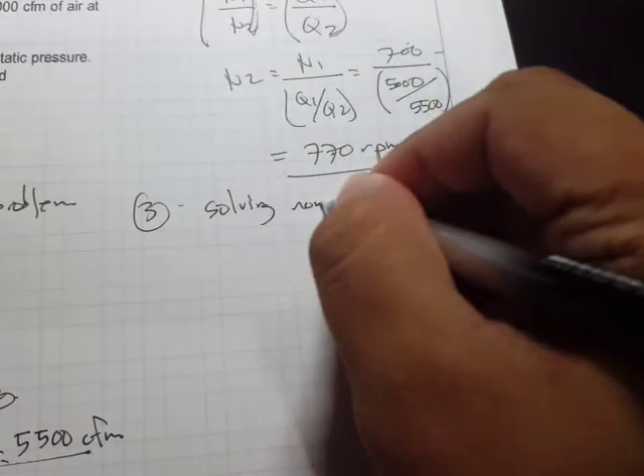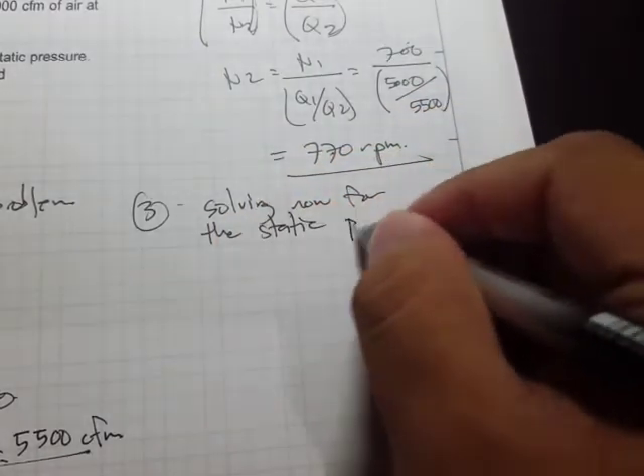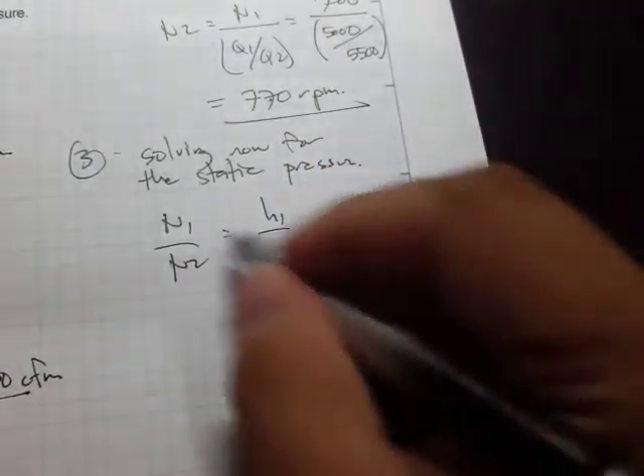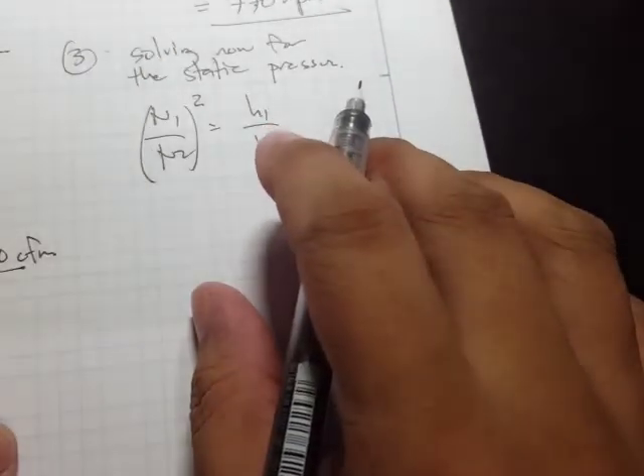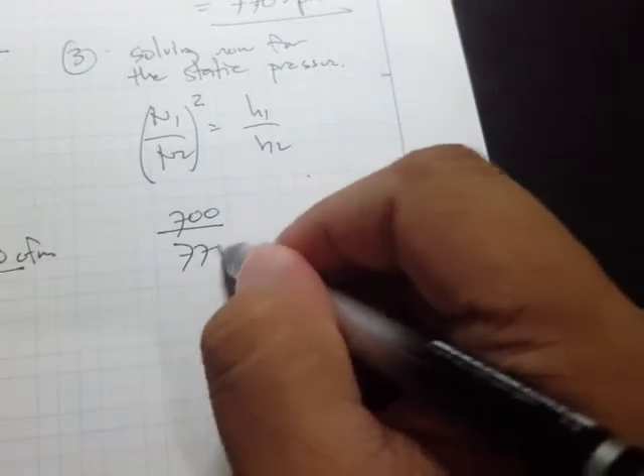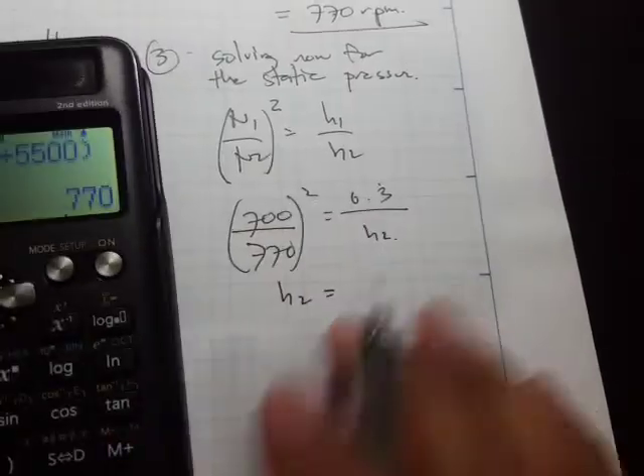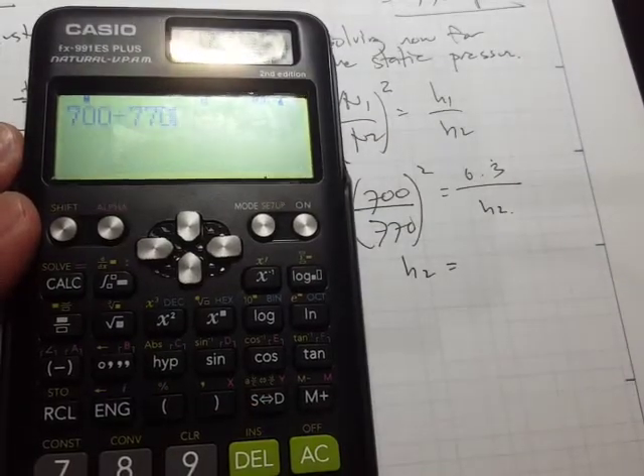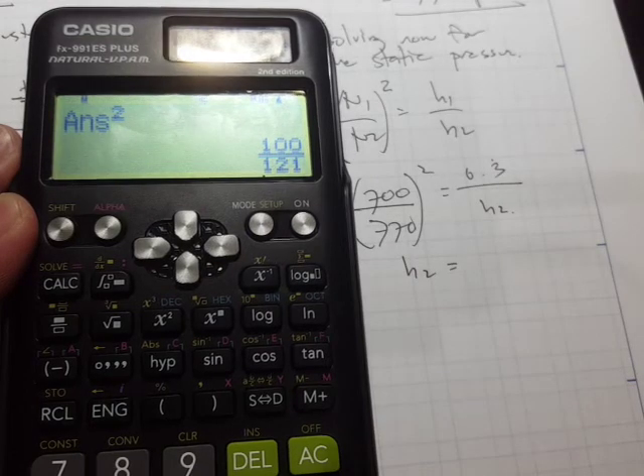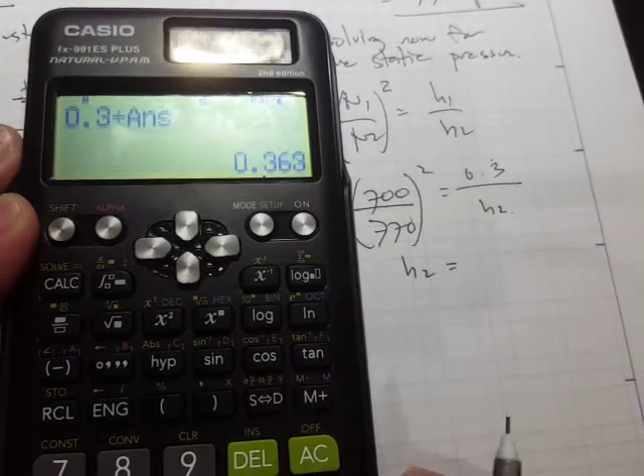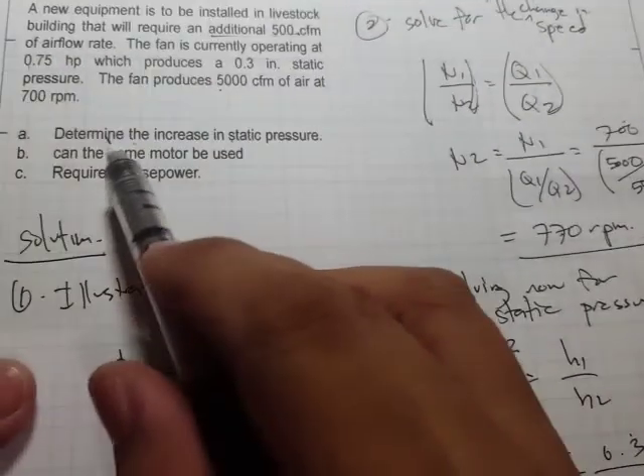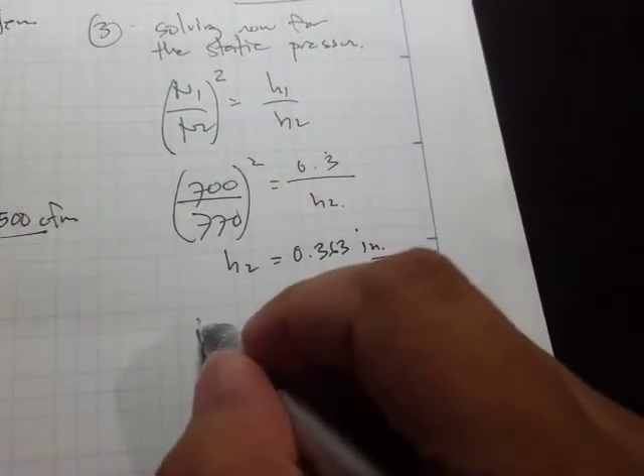From 700 RPM, the fan speed now increases to 770 RPM. Now solving for the static pressure: n₁/n₂ = h₁/h₂, and the relationship to static pressure is squared. So (700/770)² = 0.3/h₂.